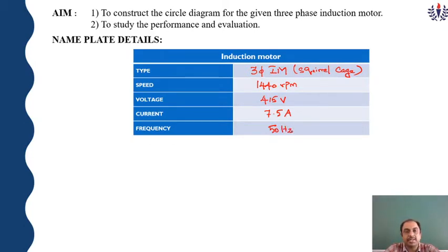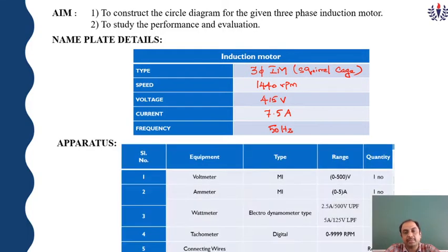To execute this in the real-time experiment, the apparatus we need: the first apparatus is the voltmeter, moving iron type, range 0 to 500, one number. Ammeter, moving iron, 0 to 5 ampere, one number. Wattmeter, electrodynamometer type, two wattmeters, one for W1 and another for W2, two numbers. Tachometer, a digital tachometer to measure the speed in RPM, one number. Connecting wires are required.